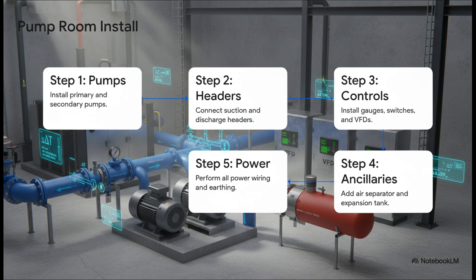Looking at the steps, first you install 2 sets of pumps, the primary pumps, which just loop water through the chiller, and the big secondary pumps, which are the ones that send it out into the building. Step 2 is connecting the headers. You can think of those as big traffic circles for water.